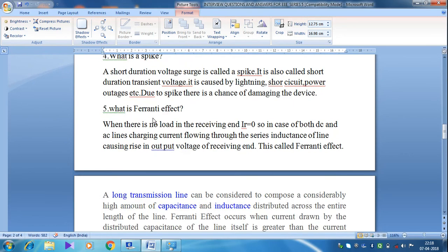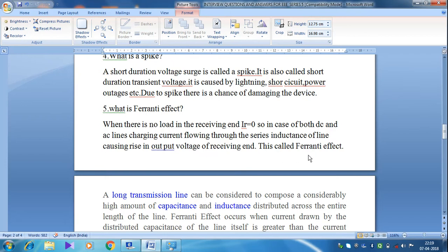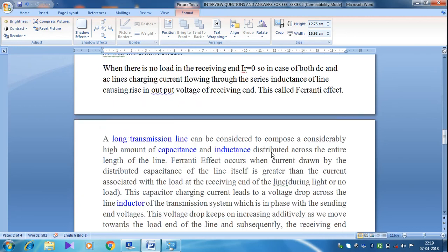The next question is: what is called the Ferranti effect? When there is no load at the receiving end, the receiving end current is zero. In both DC and AC lines, the charging current flowing through the series inductance of the line causes a rise in the output voltage at the receiving end. This is called the Ferranti effect.